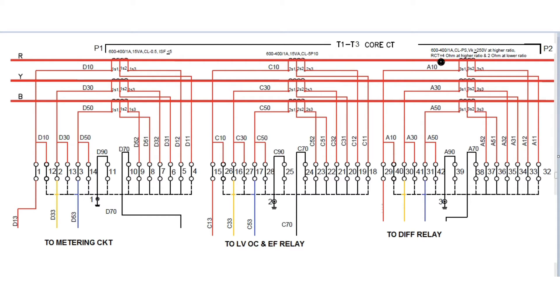The third core specification: CT ratio is the same, class is PS (protection special class), and knee point voltage is 250V at the higher ratio. RCT is 4 ohms at the higher ratio (600/1) and 2 ohms for the lower ratio (400/1).